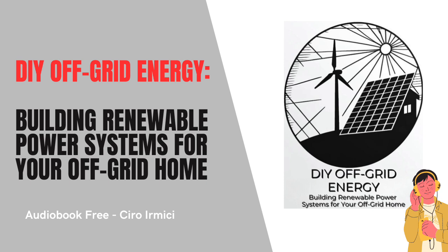Properly sizing your battery bank is crucial to ensure that you have enough stored energy to meet your needs, especially during periods of low or no power generation. Sizing involves calculating your daily energy consumption, determining the desired days of autonomy, the number of days your system can operate without additional charging, and factoring in the depth of discharge, DOD, that your batteries can safely handle.